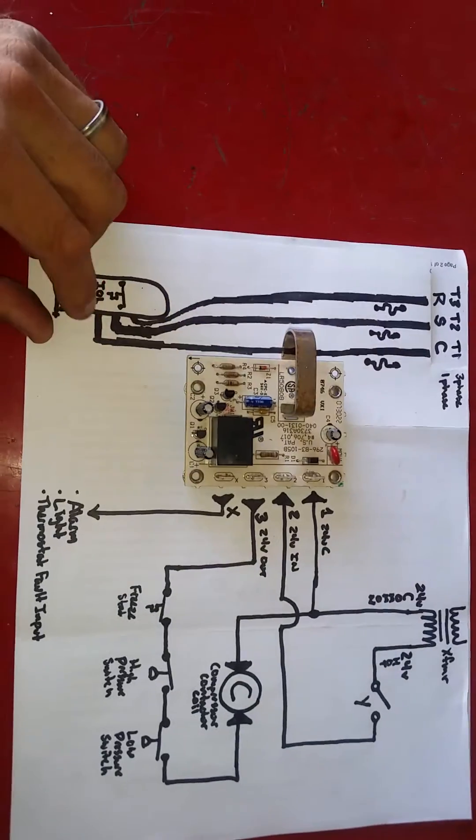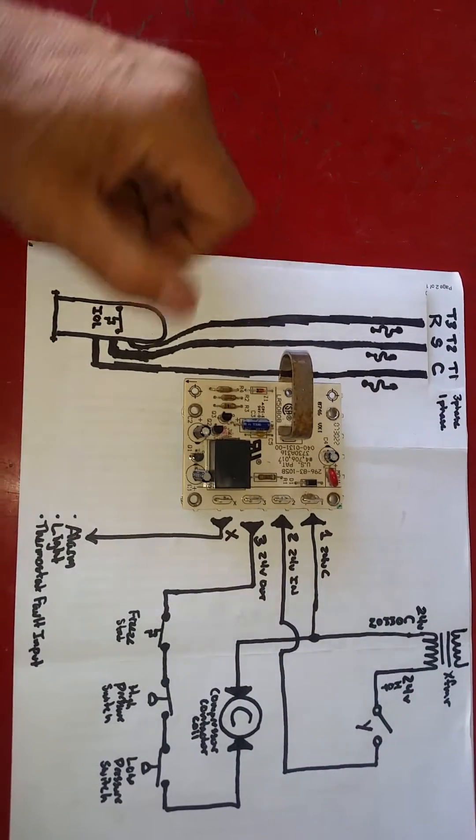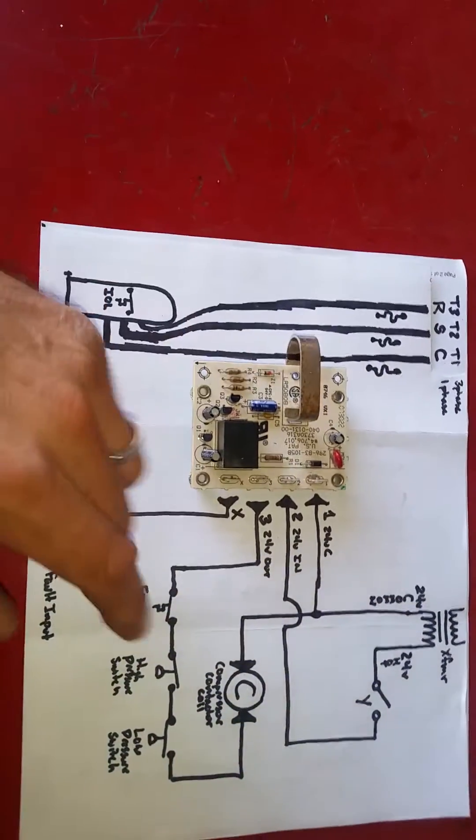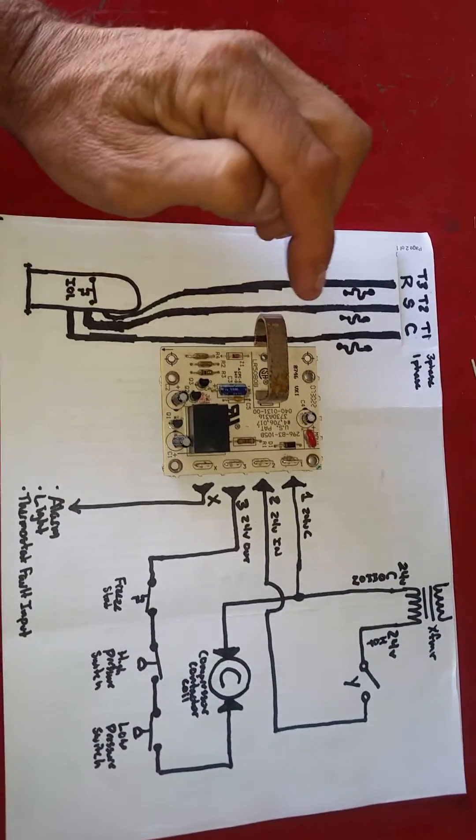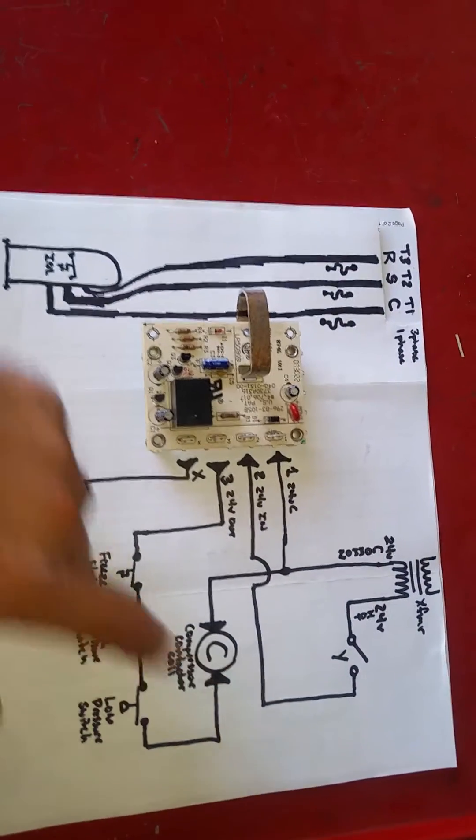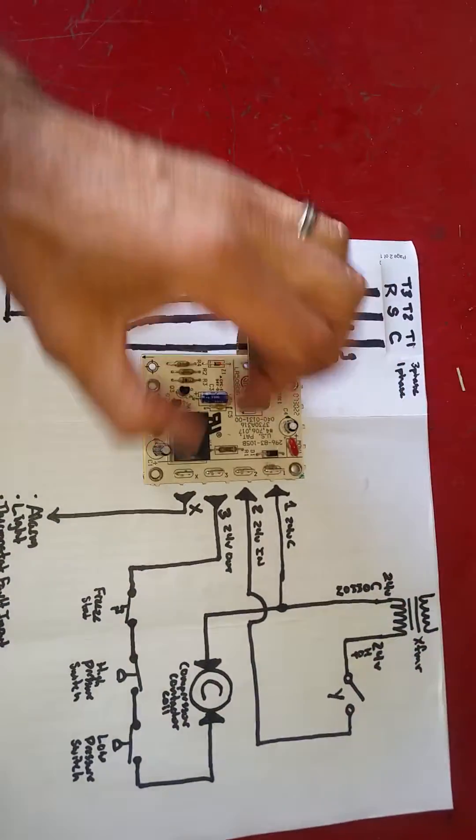We may also have an internal overload inside our compressor that opens, causing the compressor to shut down. It is no longer drawing current through the sensor. And again, the circuit may open. So in essence, a CLO, a current lockout is monitoring current. When the safety is open, the compressor shuts down, no current, lockout condition. If a fuse opens, no current, lockout condition.